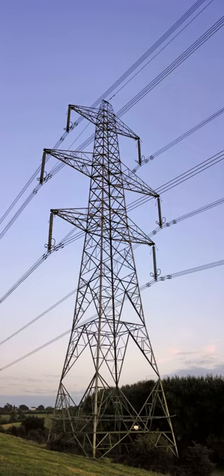Lattice. A lattice tower is a framework construction made of steel or aluminium sections. Lattice towers are used for power lines of all voltages, and are the most common type for high-voltage transmission lines. Lattice towers are usually made of galvanized steel.